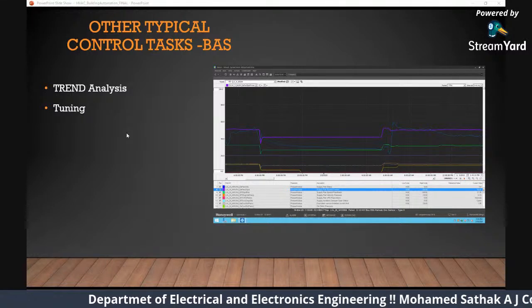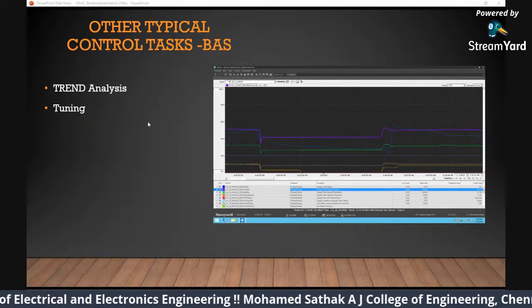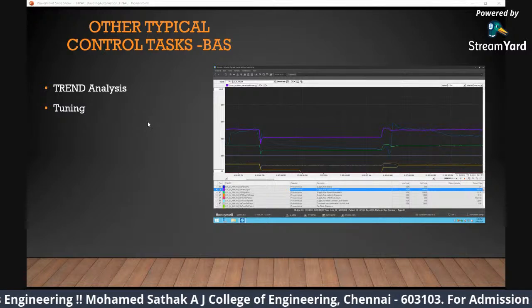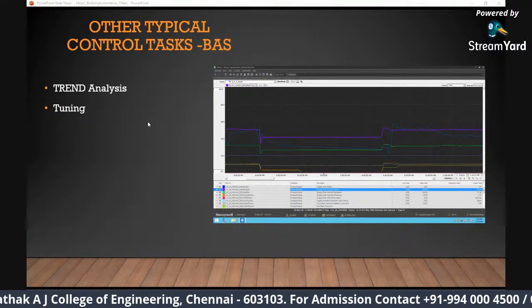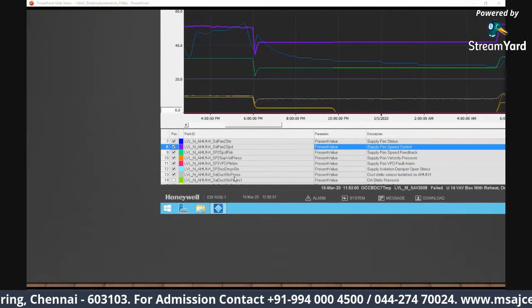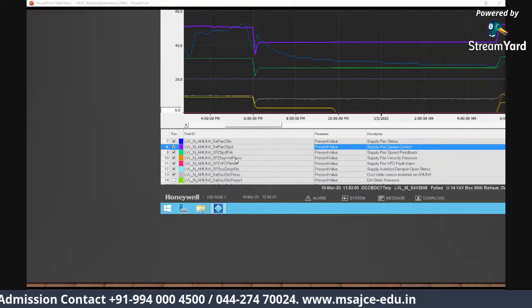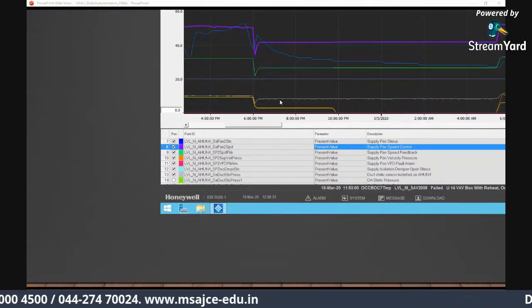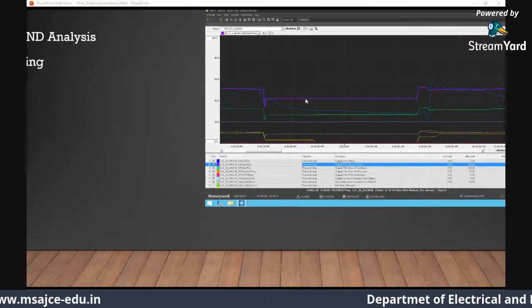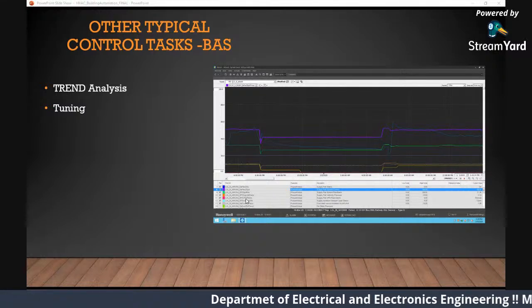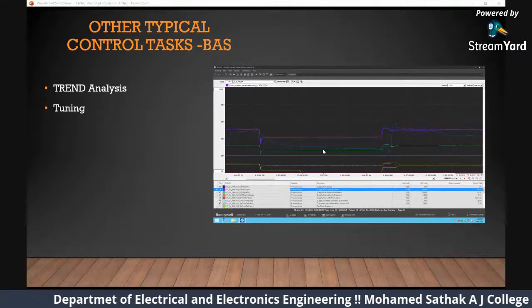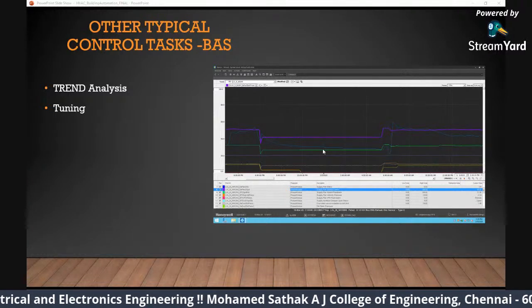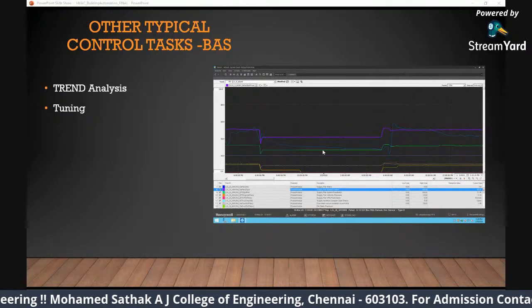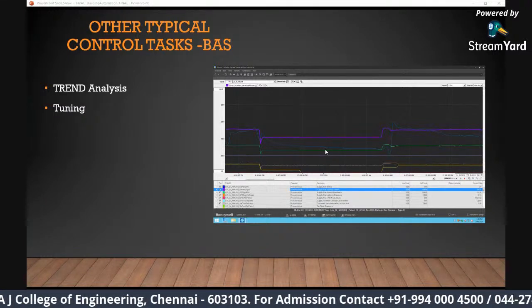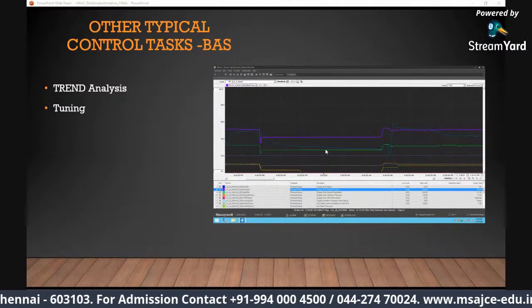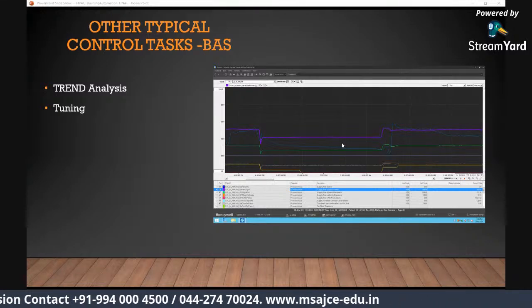Apart from that, we have something called trend analysis and tuning. Let's say a pump or a fan is not performing good. So we have to monitor individual points. Can zoom in on this. So we monitor the status, speed, feedback, pressure, damper status, everything on the front end. This is how a front end looks, and this is a trend analysis screen. So we monitor every point on the front end, make sure it's operating good, and we tune. Tuning is again an important concept, a part of the instrumentation industry. You have to tune it so that the damper or the parameters are maintained good. We do that through trend analysis.